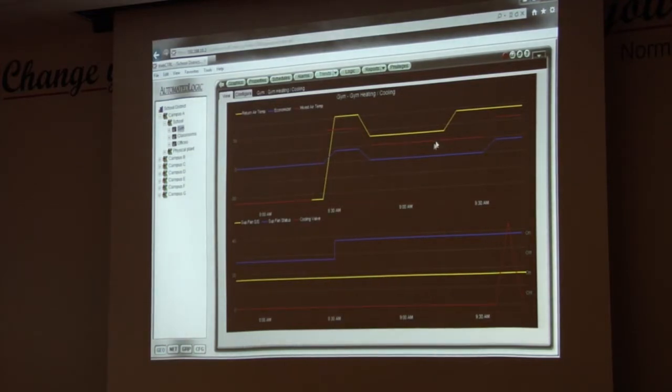Well, there's my return temp. I could see it was coming in higher, as it's supposed to. Then by the time it hits the mixed temp, it's supposed to be even less than that. When I hit the mixed air, well, here you have a return. Then we have the economizer damper position, and we can see that my mixed air temp is lower. This is the way that it should be.